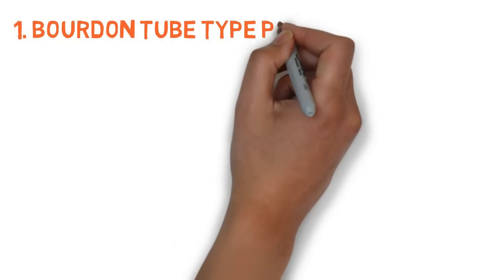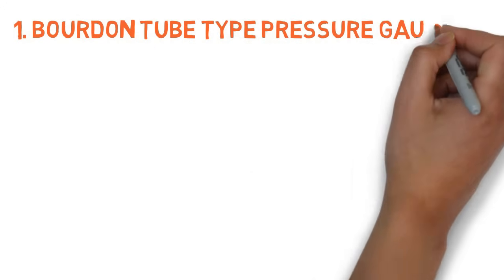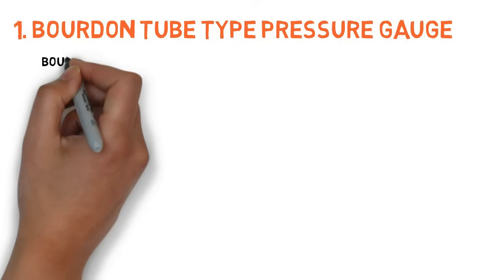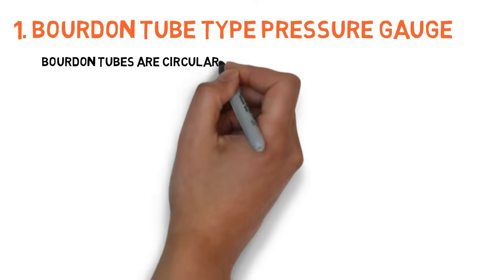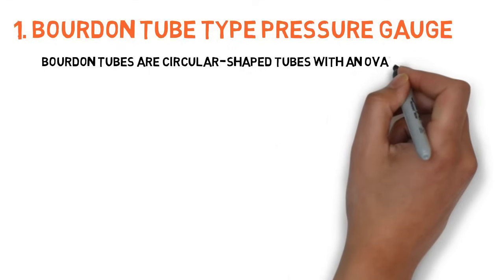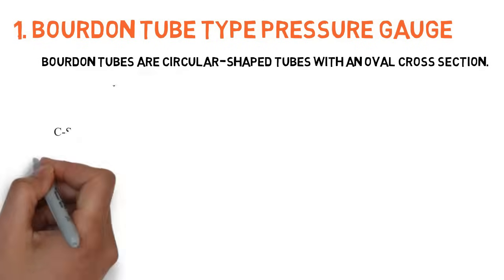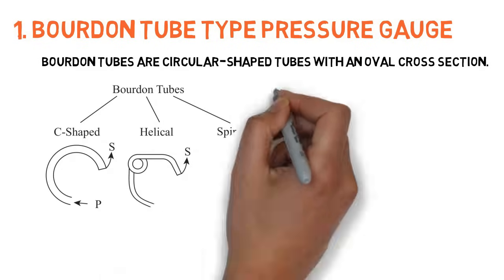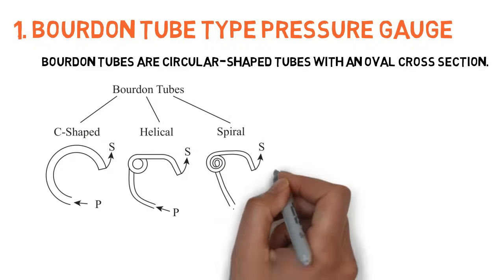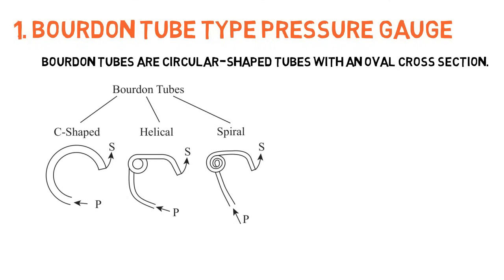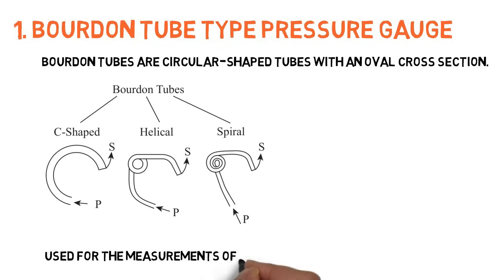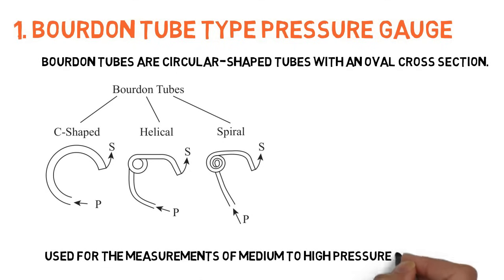Bourdon tube type pressure gauge. Bourdon tubes are circular shaped tubes with an oval cross-section. Bourdon tubes are manufactured in three different forms: C type, spiral type, and helical type. Bourdon tube sensing elements are used for the measurements of medium to high pressures.